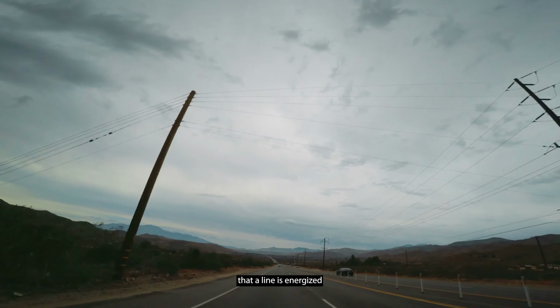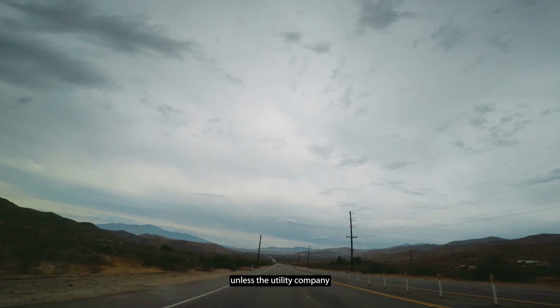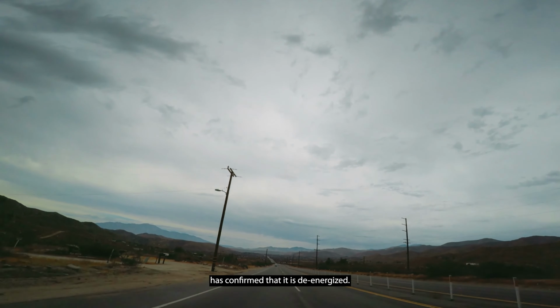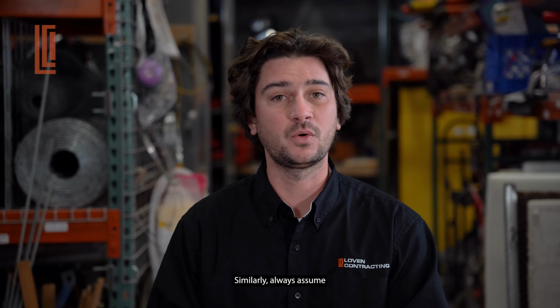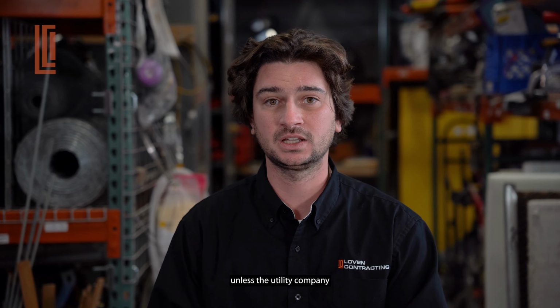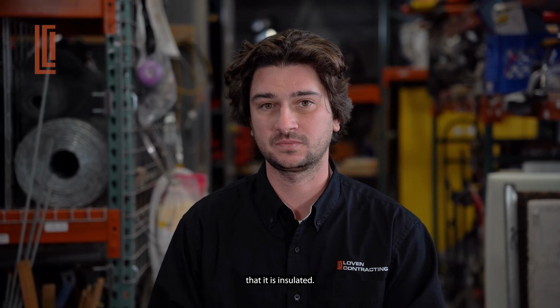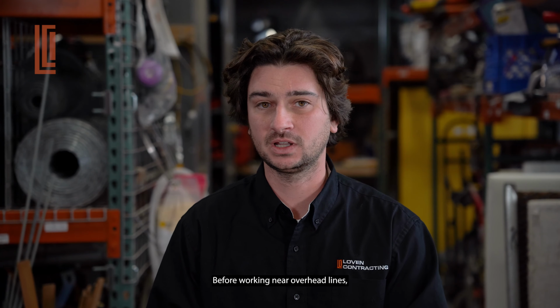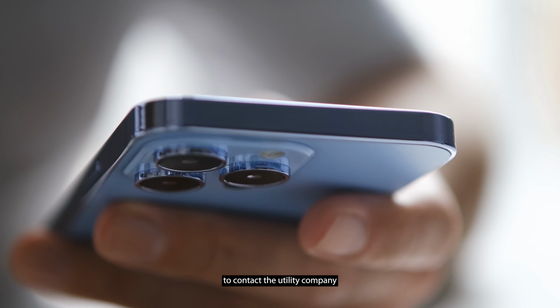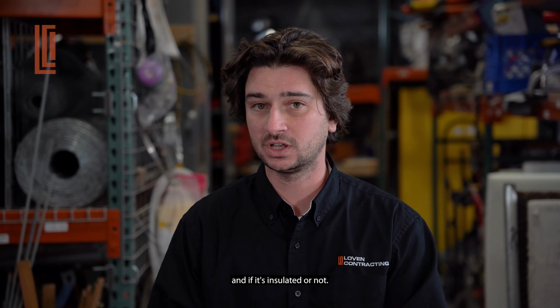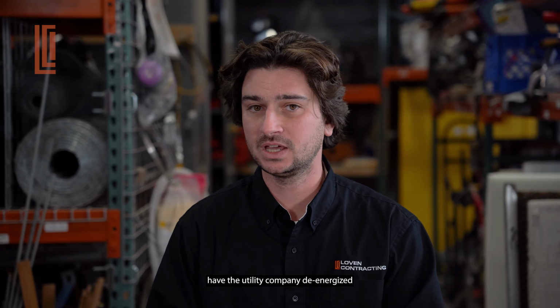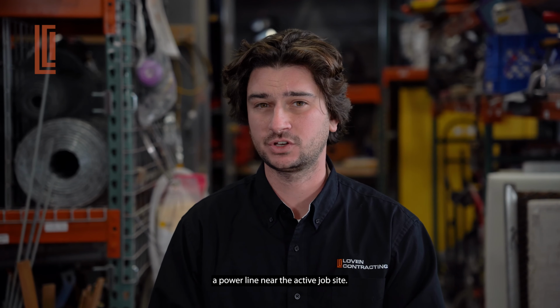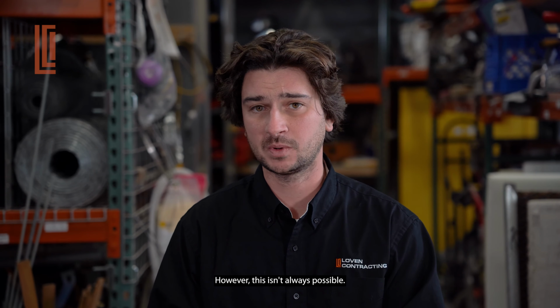Remember to always assume that a line is energized unless the utility company has confirmed that it is de-energized. Similarly, always assume that a line is uninsulated unless the utility company or qualified engineer confirms that it is insulated. Before working near overhead lines, it's important to contact the utility company to confirm the line voltage and if it's insulated or not. If possible, have the utility company de-energize a power line near the active job site. However, this isn't always possible.